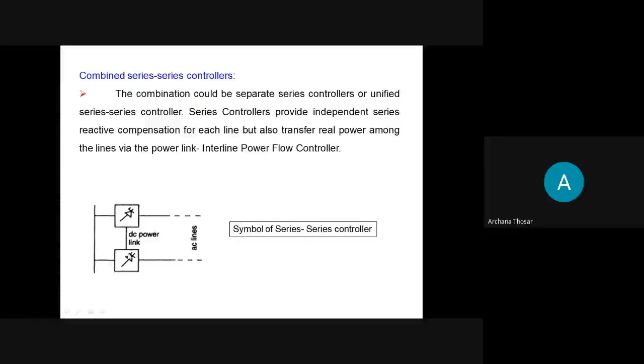Then in a combined series controller, there will be one converter in series, another converter in series, and their DC link will be tied together. So their DC link will be common. So this is called an interline power flow controller. Okay. Then the next is the combined series and shunt controller. So now here one controller is connected in series, and another converter, a FACTS controller or a converter, anything you can say, is connected in parallel to the line, and this is coordinated by a single converter, a single controller, I mean, and hence it is taking the benefit of both the series and the shunt controller.